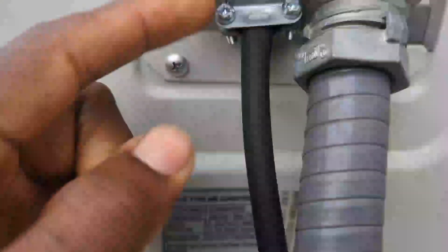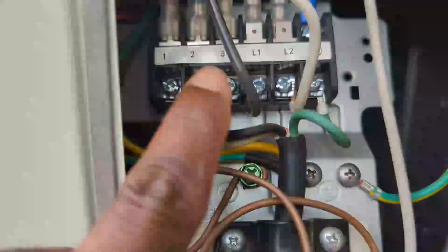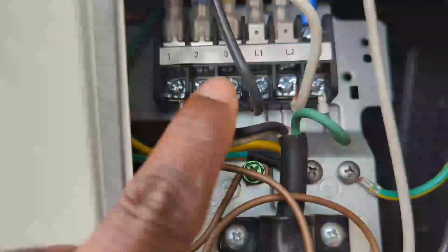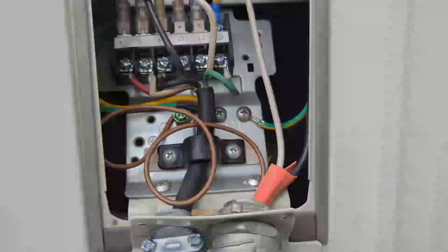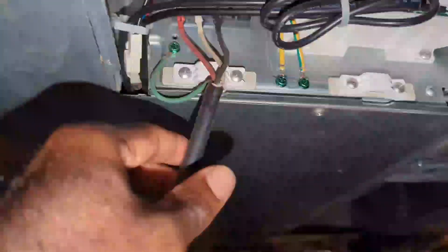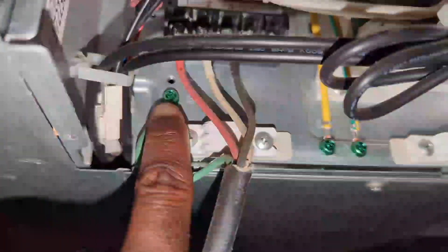Ground goes to the ground screw. This wire goes to the dock on the outside unit — red goes to one, white goes to two, black goes to three, and ground is ground. You do the same thing for the inside unit: ground goes to the ground screw, red goes to one, white goes to two, and black goes to three.